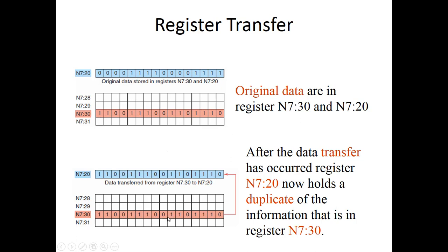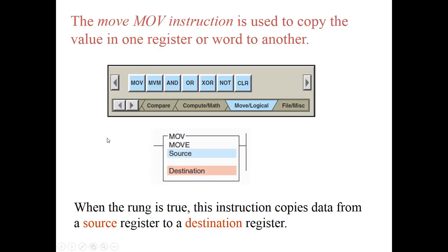We're basically moving these words around. Okay, and N for an SLC 500 is where you store word data. N7, just like counters were C5, timers were T4, bits were B3. If we just have a word, some data, we can store those in these locations, N7.